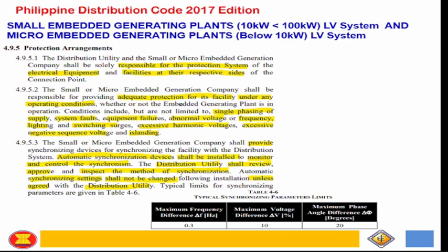if it's a three-phase system and a problem happens there, it's not the responsibility of the distribution utility, whatever happened to their system. Your protection is not limited to single phasing supply, system faults, equipment failure, abnormal voltage, frequency, lightning, switching, excessive harmonic voltage, excessive negative sequence, as mentioned, and then islanding. And an automatic synchronization device shall be installed to monitor the control of synchronism.